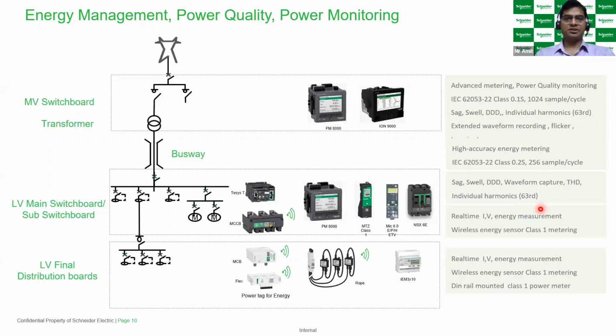And finally, in the LV distribution, if you want to monitor the consumption of your OT or ICU rooms, let's say how many surgeries have been done based on the power consumption, there is a device which mounts directly on your MCBs. No cabling is required, no connection is required. It will directly mount on your MCBs, and it will give you the complete current, voltage and energy parameters.